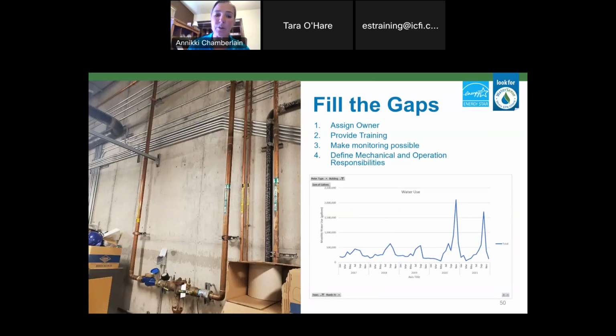So what can we do to get this into normal routines? We need to assign an owner of the property, and provide a little training that when we see overflow, it's bad, or how to read the reports. Not a ton of training, an hour would do it. There's a water makeup meter inside the building. Can we incorporate that into some kind of round so we can at least be writing that down every day and seeing if there are these big spikes?